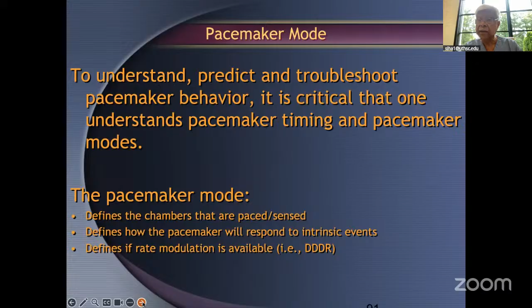If there is no QRS complex, then the pacemaker fires. If there is a QRS complex, it will not fire. That's the demand mode. So it defines the chambers that are paced and sensed, and how the pacemaker will respond to the intrinsic events. And sometimes we put R at the end that defines if rate modulation is available in that pacemaker or not.